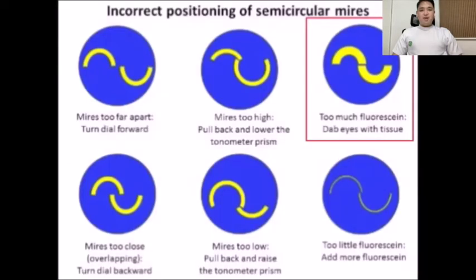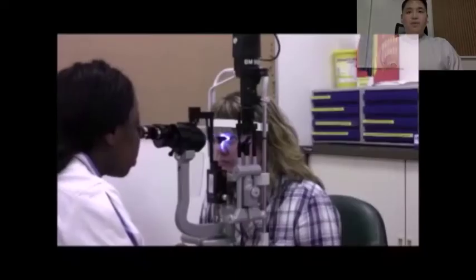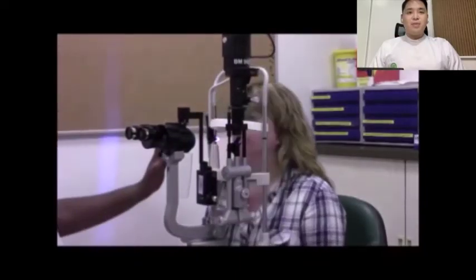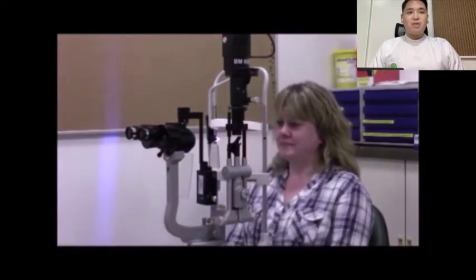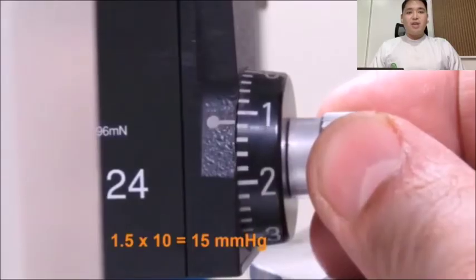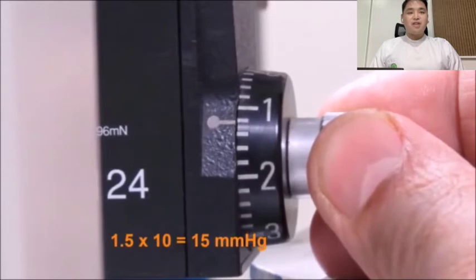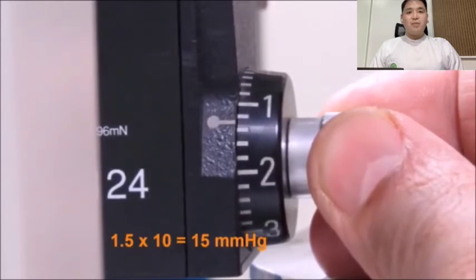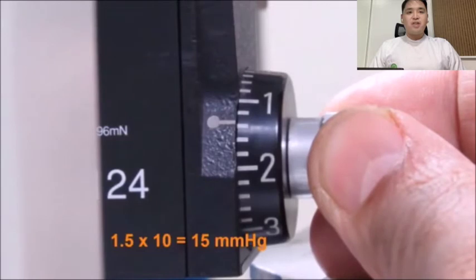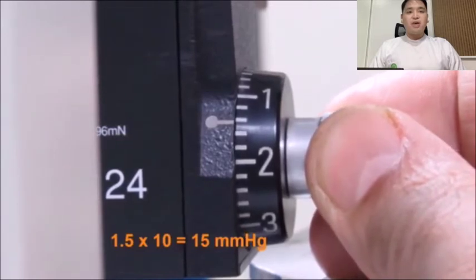If there is too much fluorescein, or if the examiner is applying pressure to the globe while holding the patient's eye open, the semicircles will appear thick and an inaccurate pressure reading will result. With the slit lamp control handle, pull the tonometer biprism away from the patient's eye. Note the reading on the number dial of the force adjustment knob. Multiply the number by 10 to obtain the intraocular pressure in millimeters of mercury, and record the pressure in the patient's chart. Repeat this procedure on the other eye.